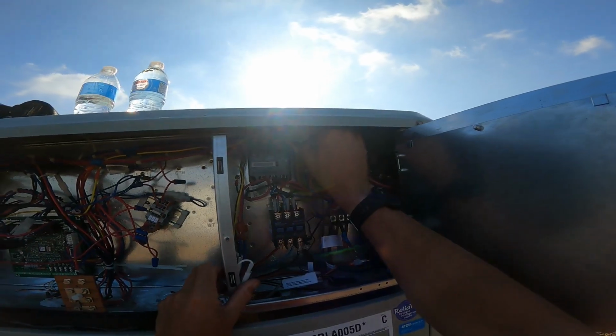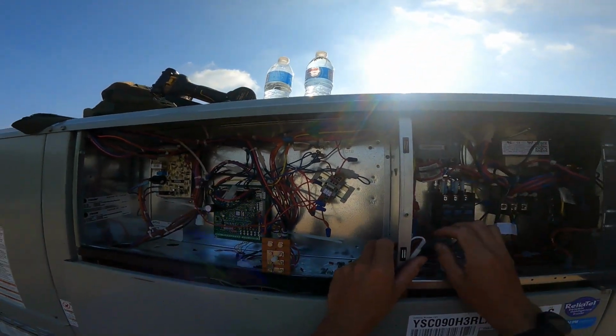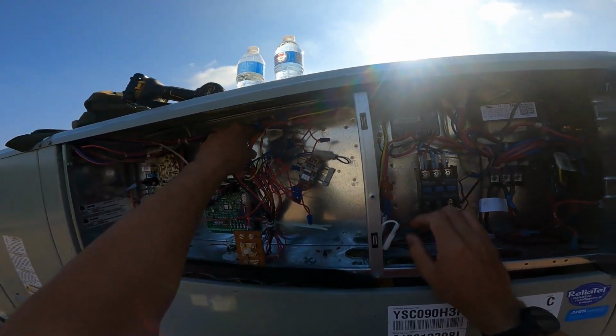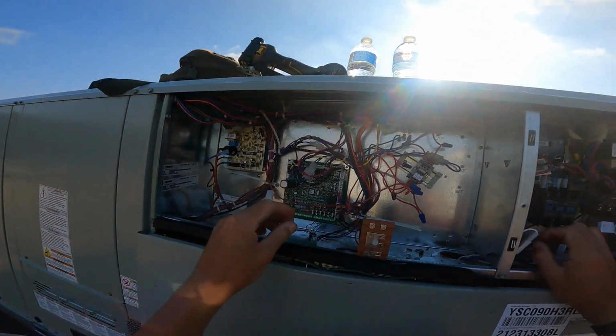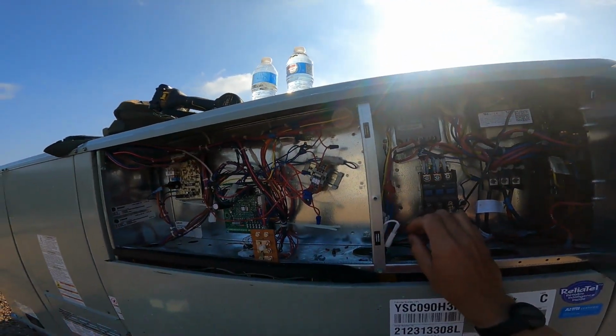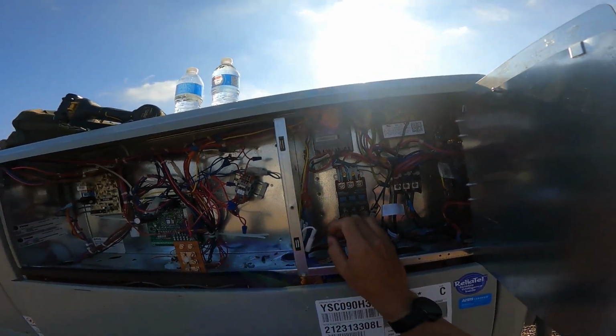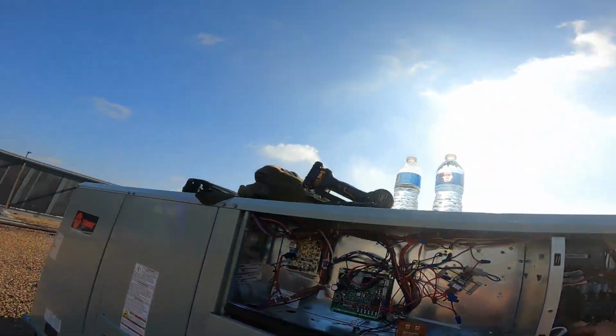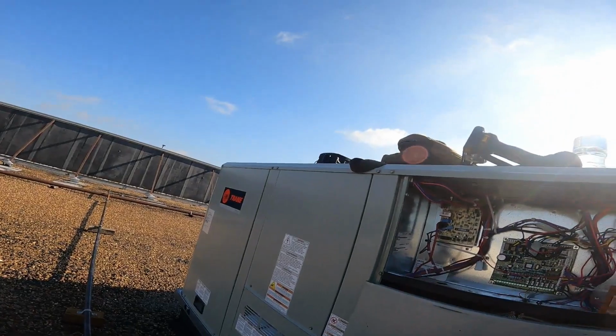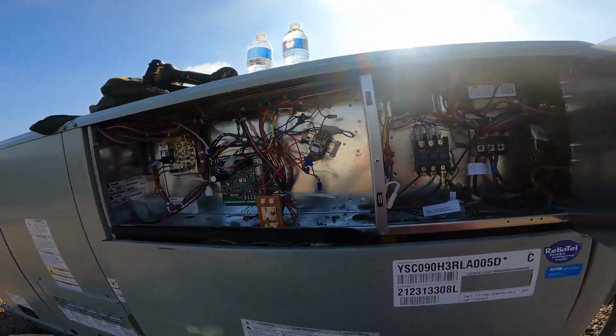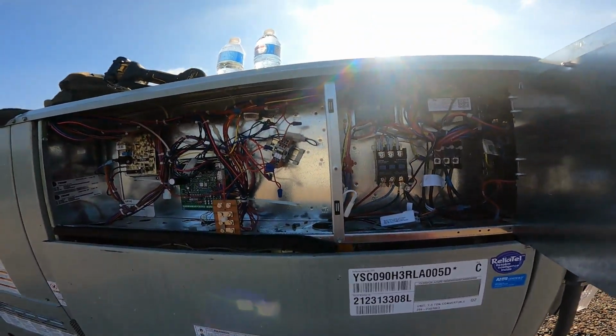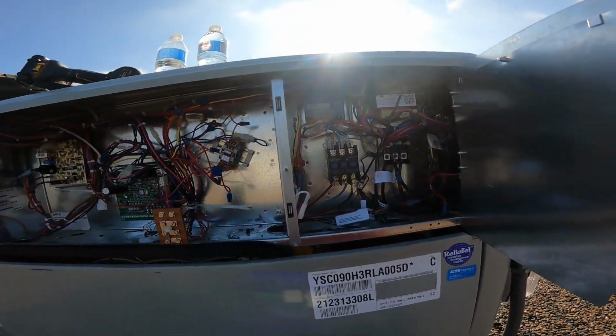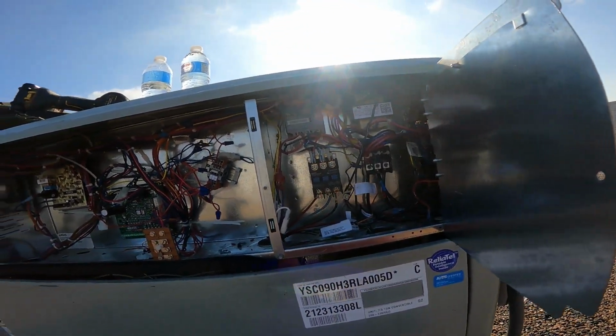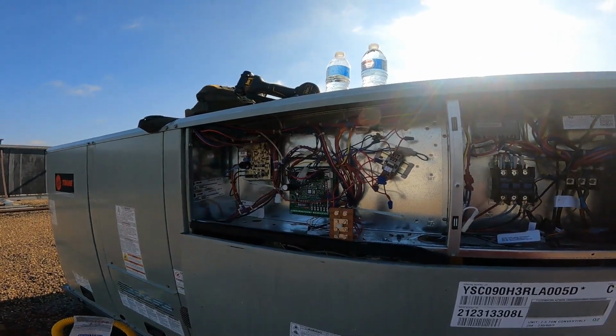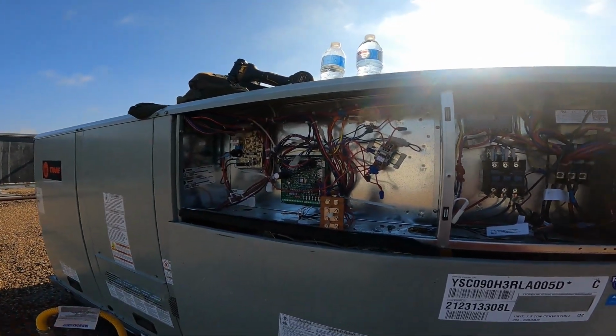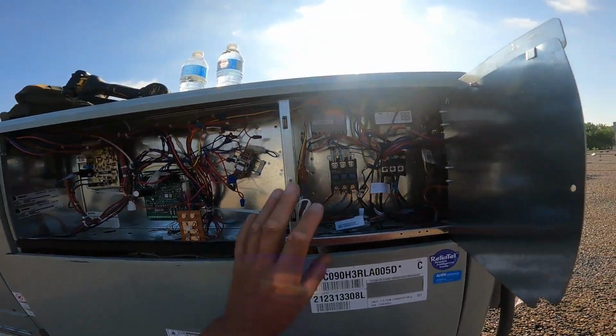Sometimes if you follow your 24 volts, somewhere between the transformer and the control board you should have a fuse, if that's not resettable. I'm not seeing one. Fellas, dudes and dudettes, I don't know what to tell you, because we'll fry that transformer, and the transformer will fry the board if that's grounded.